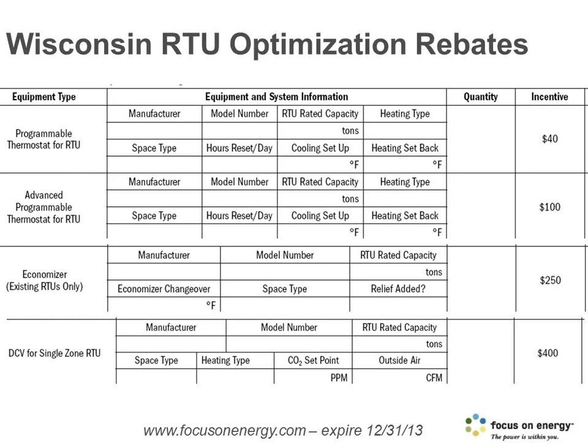You get a rebate of either $40 or $100 for the programmable stat. To get the bigger rebate, the programmable stat has to have the ability to interlock its occupancy to the rooftop economizer minimum position. So there are thermostats that do that. We did put a list of them on the FAQ section of the utility website, so you can see what those model numbers are. And on there, I did list what terminals you wire to and what settings and jumpers you move and all that stuff. So check that out, or ask me for help if you need something in Wisconsin like that.